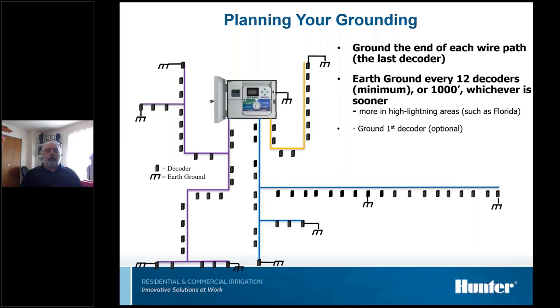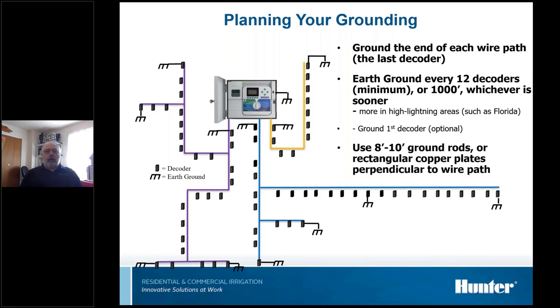Optionally, and we've learned this in recent years, it makes a lot of sense to ground the first decoder on each wire path. This is another effort to protect the controller. And we've also found that for whatever reason, that first decoder on the wire path is the most likely one to fail. So it seems logical to put a ground rod there too. Again, that's just an option. You don't have to, but if you're looking to help your system out, that's a good idea.